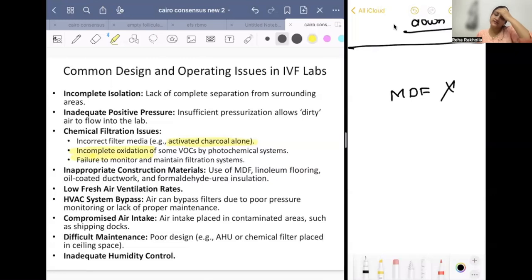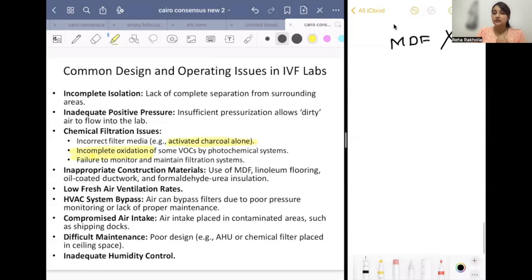Formaldehyde urea insulation was previously used - we would take formaldehyde urea and insert it between walls for insulation. But in IVF labs we cannot do that because there will be off-gassing of formaldehyde, which is a VOC and not at all good for gametes and embryos.